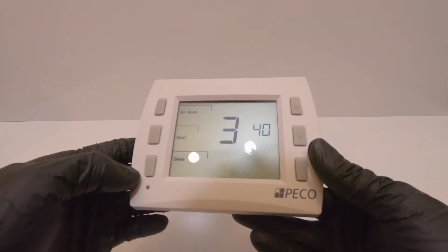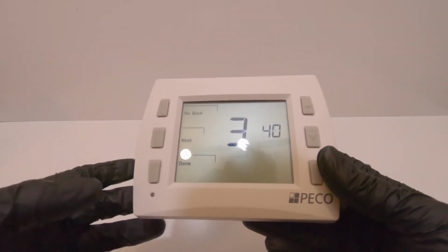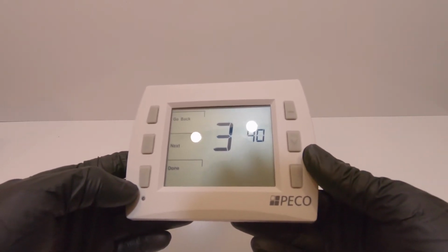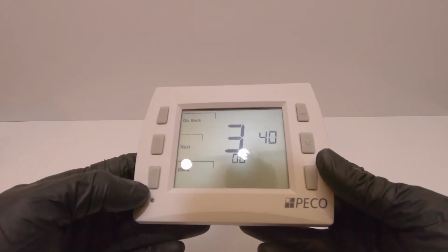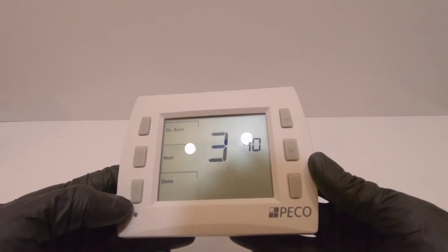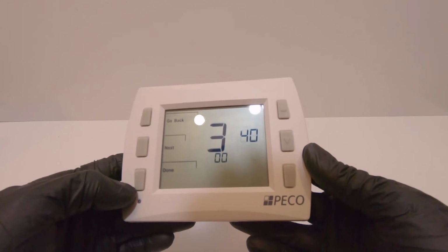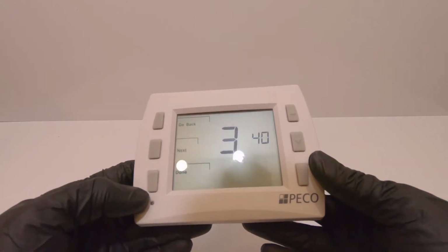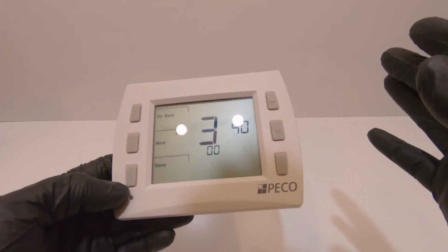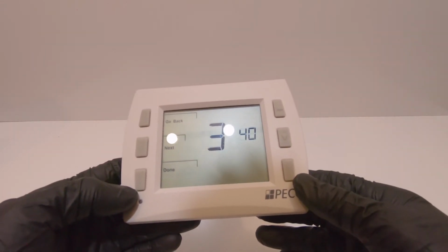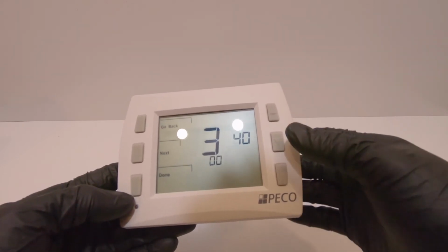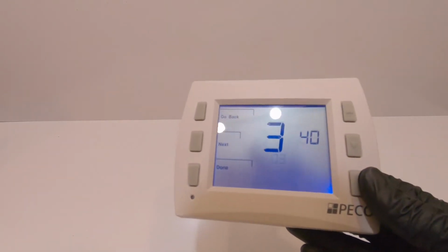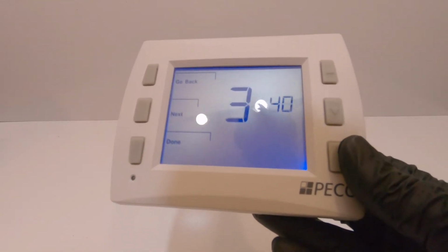I don't know what pulls people to the thermostat, but in certain situations it's kind of a big issue. And then in other locations, nobody touches it. They've been told, hey, keep your hands off. So for this particular setting, it's going to be 00, which is no keypad lockout, which is the default, or you can go to 03. And what that's going to do is lock out all of the keys.